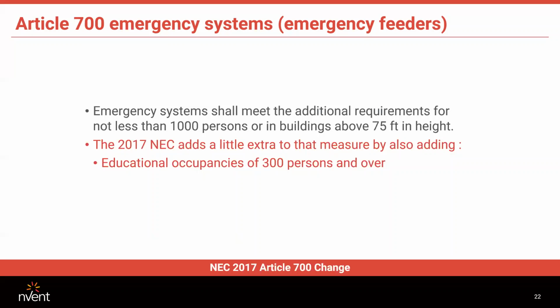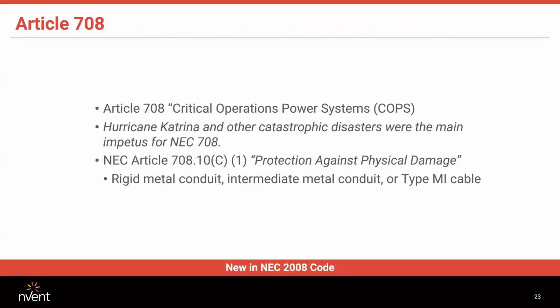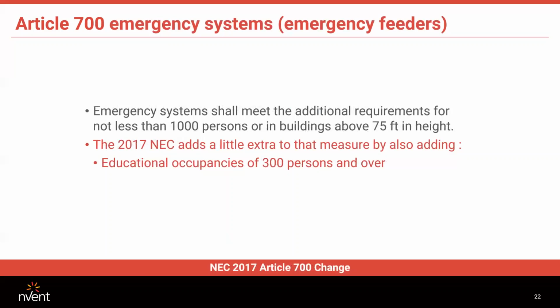Also, the 2017 NEC added that educational occupancies of 300 persons or over are also required to have 2-hour fire-rated emergency feeders. So that's pretty much going to be just about any school you're working with, or most schools. They will be required to have fire-rated emergency feeders. That's important to know about. Most people knew about the height requirement, above 75 feet, or greater than 1,000 people, but this is one a lot of people are just becoming aware of. So again, if you have a school with 300 or more people, those emergency feeders will need to be fire-rated.